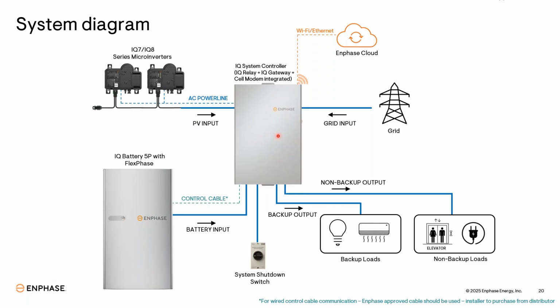From your controller, you will take your backup output and your non-backup output. For the loads which you want to back up, you will take a separate line and neutral from here, and the loads you do not want to back up, you can take from here also. So both have a separate line and separate neutral cable. One wire will go towards your system shutdown switch. This is an emergency switch. Once you turn this switch off, your complete system is going to shut down.